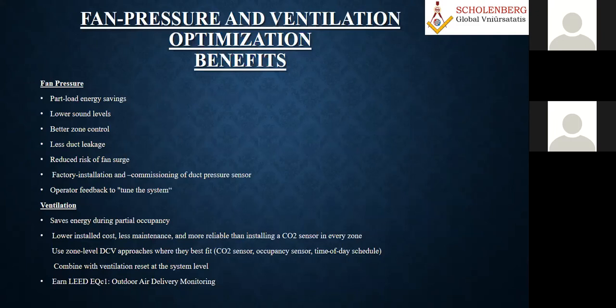Similarly, there is an optimization benefit when you try to optimize the fan pressure. Yesterday, Dr. Yad was slightly telling, when I was talking, you also asked some question: sir, when I put so many filters, what type of pressure drop? He is an expert on the filtration side, so he looks only from the filtration point of view. But you, being an air conditioning engineer, when I put pre-filters, fine filters, even HEPA filters, ultra filters, everything, when you add it, definitely the pressure drop across the system will increase. So all that you have to find out.